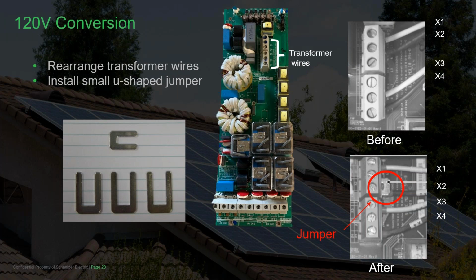First step in 120-volt conversion is moving the transformer wires and installing the small jumper. Note the AC board is displayed with the location of the transformer wires identified. On the right, you can see the before and after photos of the transformer wires and their respective positions, and the location of the small U-shaped jumper. This removes the center tap lead and allows the full transformer winding to be utilized for a single 120-volt connection.